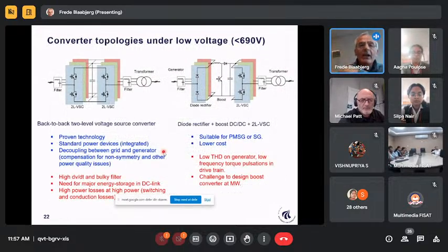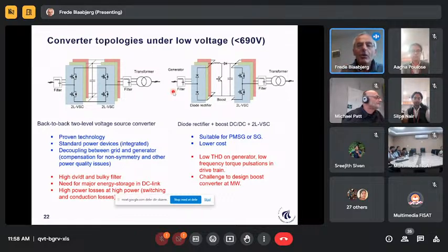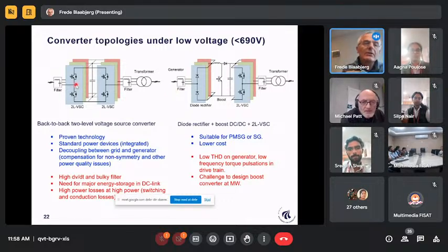The converter topologies we are applying are divided into two categories. One is below 690 volts, which gives a low voltage scenario in terms of implementation. In the power electronics area, this is a two-level voltage source converter which is applied. If the generator has synchronous generator characteristics, meaning the voltage is generated by the generator itself, then we do not need an active converter to control the frequency and so on. There we can just apply a boost converter, and then we have a DC to AC converter to the grid side. This is really used a lot, and also used in a lot of other industries.